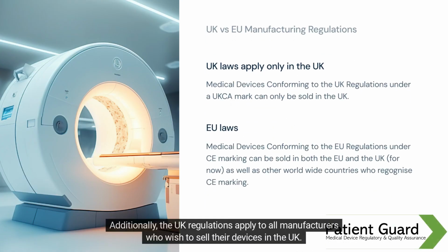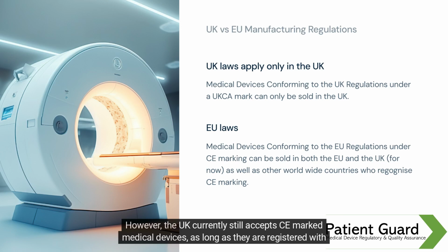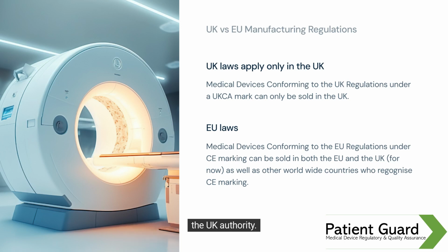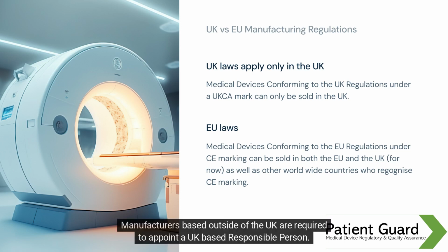Additionally, the UK regulations apply to all manufacturers who wish to sell their devices in the UK. However, the UK currently still accepts CE-marked medical devices as long as they are registered with the UK authority. Manufacturers based outside of the UK are required to appoint a UK-based responsible person.